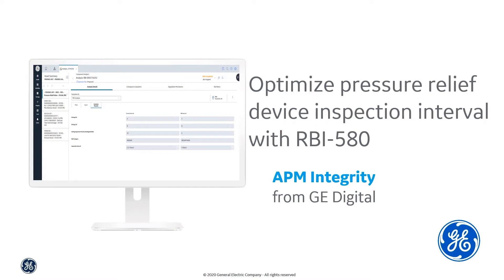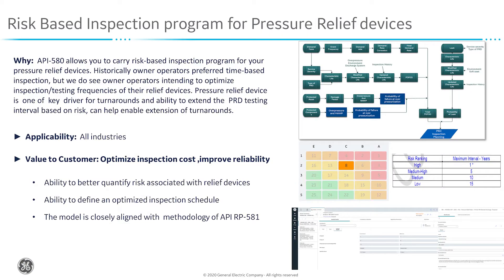Hello and welcome everyone to this session where we will talk about how to optimize your inspection interval for pressure relief devices using RBI 580. From a value perspective, the question is why? API 580, or American Petroleum Institute's Recommended Practice 580, allows you to carry out a risk-based inspection program for your pressure relief devices.